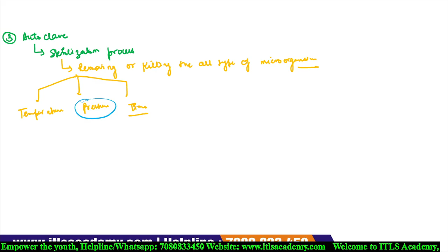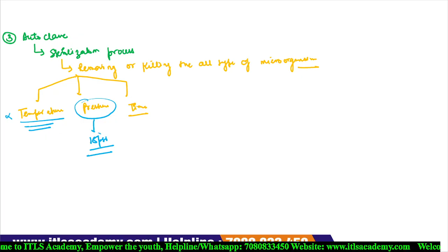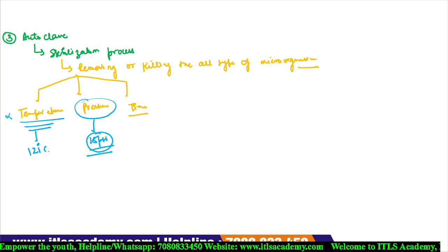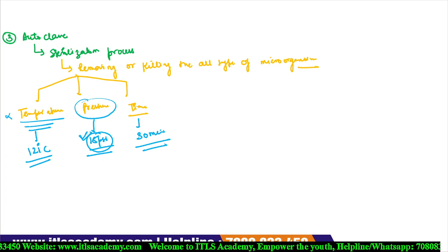It means that when we perform autoclaving, the pressure should be 15 psi, and when 15 psi pressure is reached, at that time the temperature reaches 121 degrees Celsius, and the time is around 30 minutes. We assume that the temperature inside the autoclave is around 121 degrees Celsius, and then we have to wait 30 minutes for the sterilization process.